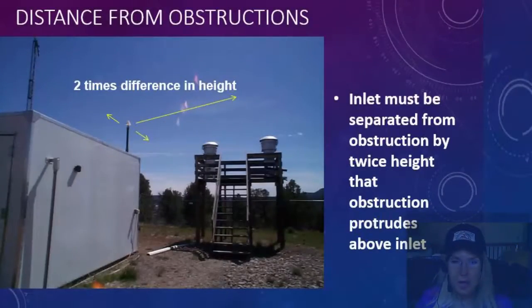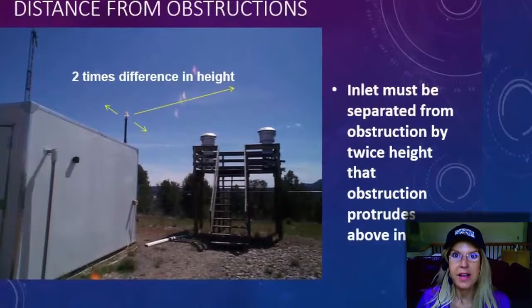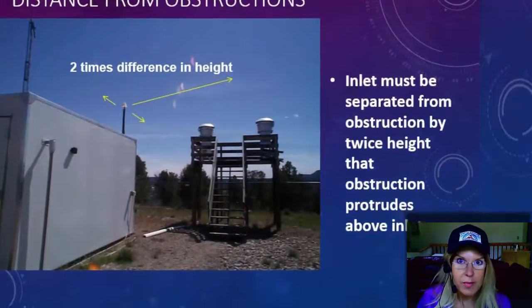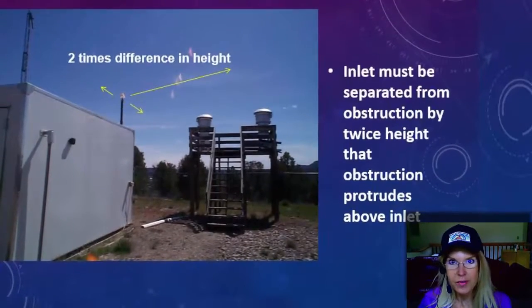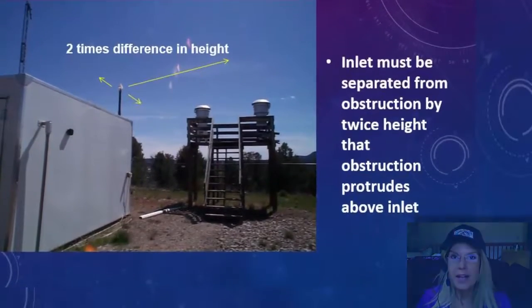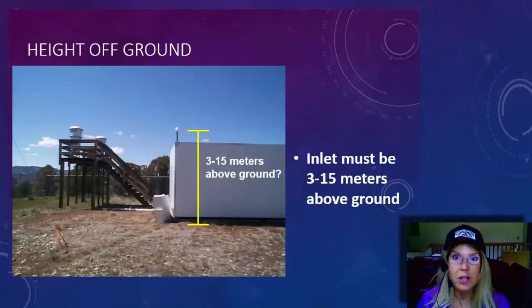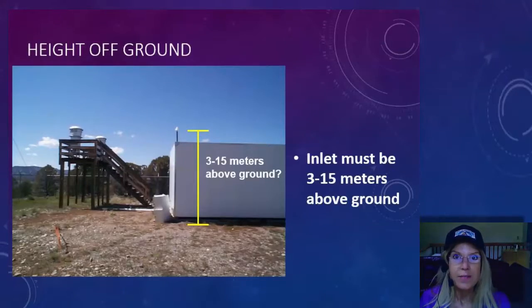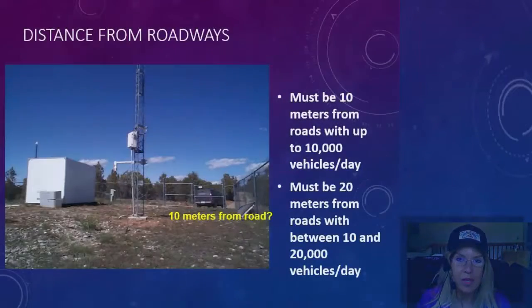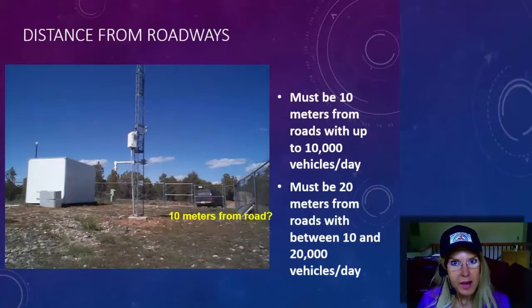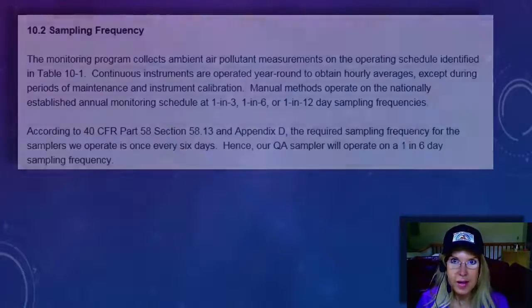Also, the actual probe itself. So where is it that you're actually sucking the air from for ambient air quality monitoring, for example. You need to make sure that the actual probe, the inlet, meets the requirements. It's not too close to the ground. It meets the requirements in terms of not being too close to a road. These sorts of things, you need to just describe and say how your location meets them.